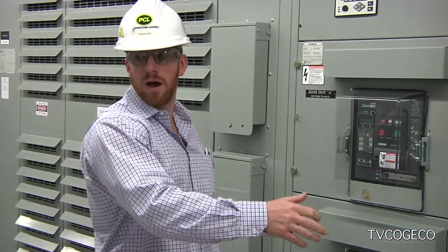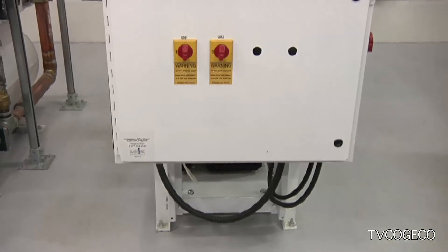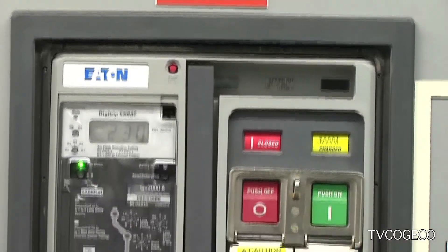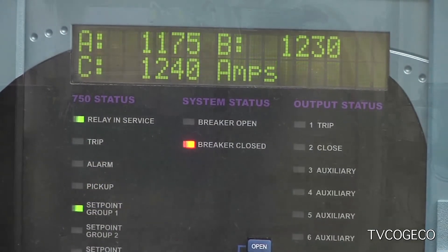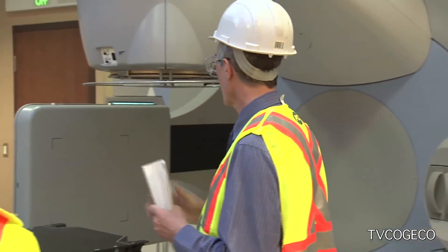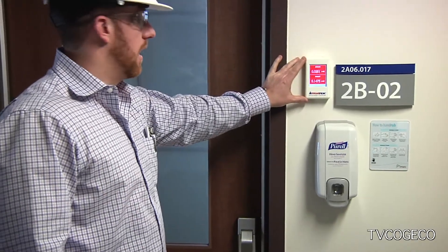So from a commissioning point of view, what's left to do? This is the phase of the project where we finalize all the commissioning process and wrap up all the outstanding paperwork. In terms of paperwork alone, there'll be about 52 three-inch binders that we'll turn over to JCI and the owner, NHS, proving that we have tested and verified that all these systems function as required. We also need to make sure that the spaces are conditioned properly and that services are available for the medical equipment now coming into the facility — your CAT scans, your x-rays, all this sort of stuff. They all have power requirements and some have HVAC requirements. We ensure those requirements are met prior to bringing that equipment in, and then the equipment manufacturers themselves come into the facility and start doing their testing.